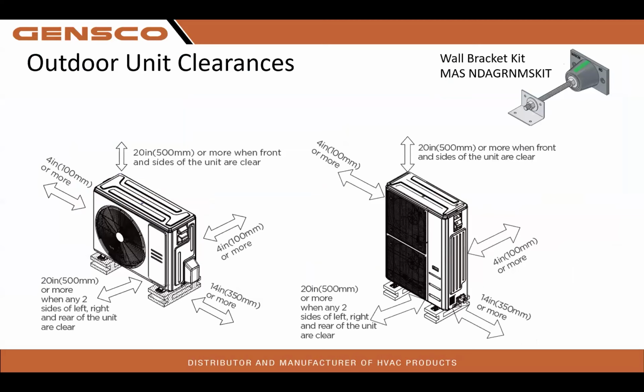Our minimum clearances when we're setting that outdoor unit. This is real nice: 4 inches from the wall of the house, 14 inches or more from any other obstructions on the sides, and 20 inches from the front. This keeps it nice and low profile for those zero clearance lot lines on the side of the house.